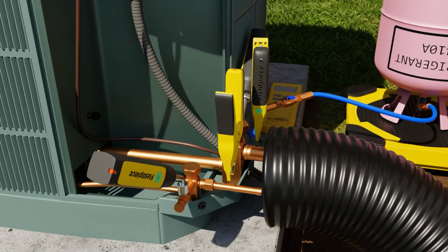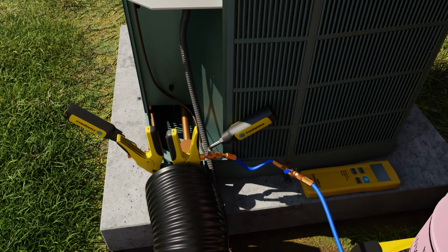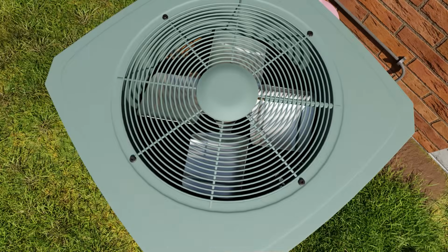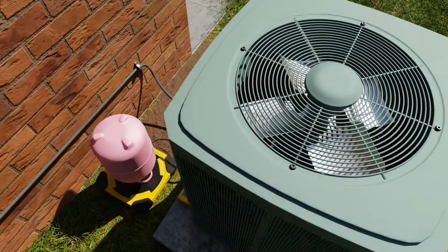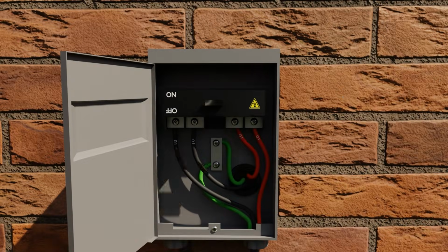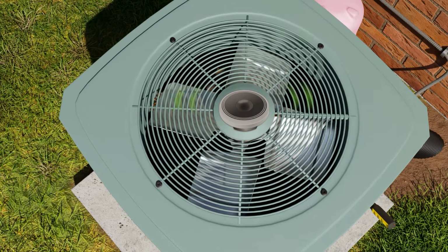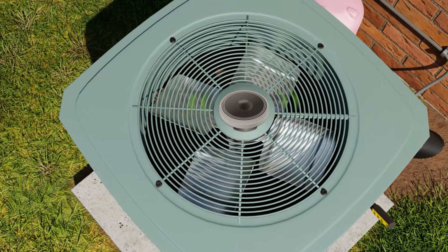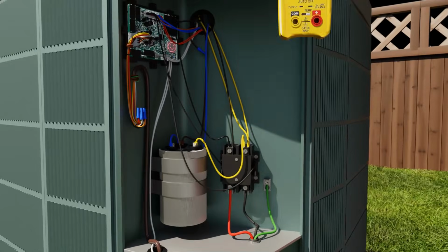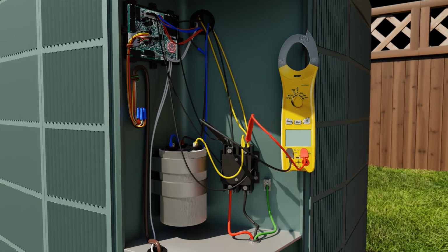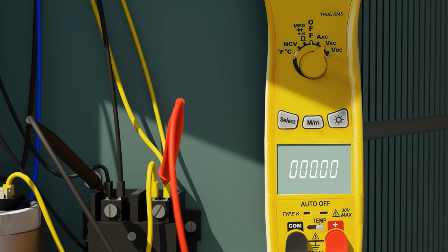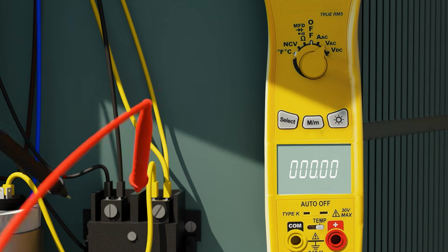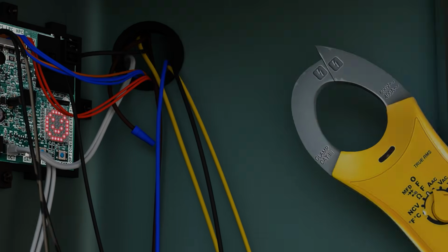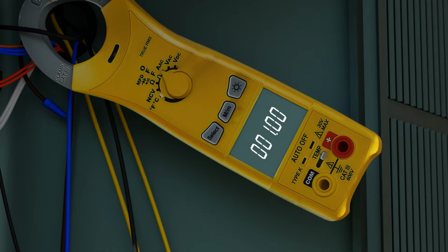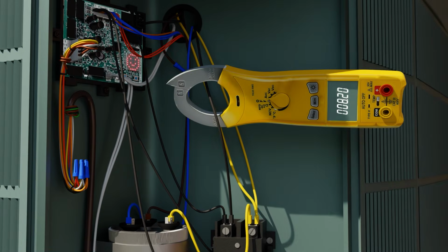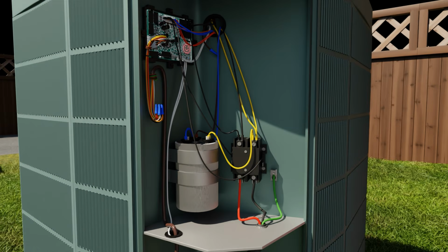Use your line temperature clamps to measure your liquid line and suction line temperatures. Now, place in your disconnect, and the system should begin running if all the time delays have expired. As soon as the system starts running, you want to listen for any abnormal sounds and be ready to pull the disconnect immediately if anything goes wrong. Now, while the system is running, you'll want to see if we have proper output voltage from the contactor. Check the amperage on your fan motor and the amperage on your compressor. Those should be below the rated amperages listed on the data plate.